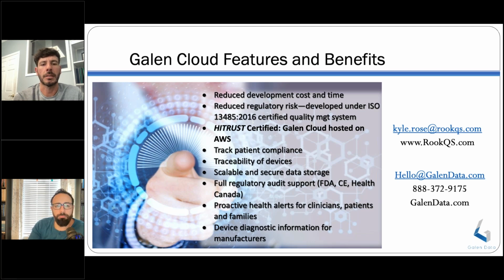Yeah, there are some exemptions for Class 1s. We would still recommend conducting a DHF or completing a DHF for the device itself to make sure that it actually works how it's supposed to. So if you're going to not complete a DHF, I would have a justification for that. And that would be more along the exempt list as well. There are certain devices that are exempt from GMP. We still recommend completing a DHF. It might not be as rigorous as a Class 2 device, but still recommended.